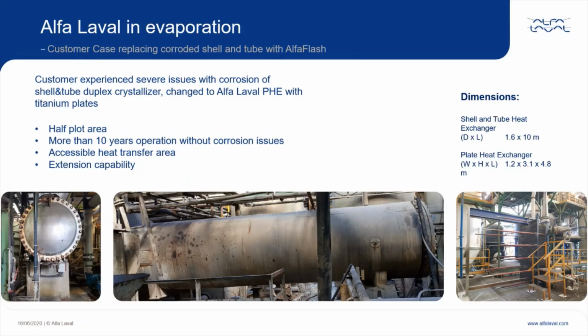Therefore, the system integrator recommended replacing it with an Alfa Laval AlfaFlash plate evaporator using titanium plates. To tackle the concerns of using plate and frame evaporators for crystallization, an AlfaFlash system with a wider gap between the plates was selected. This evaporator has achieved zero liquid discharge for more than 10 years without corrosion issues or major fouling and continues to perform. A more compact installation, the adaptability and the full access to the heat transfer area are other valuable benefits received more or less for free by our Spanish customer as part of this replacement.